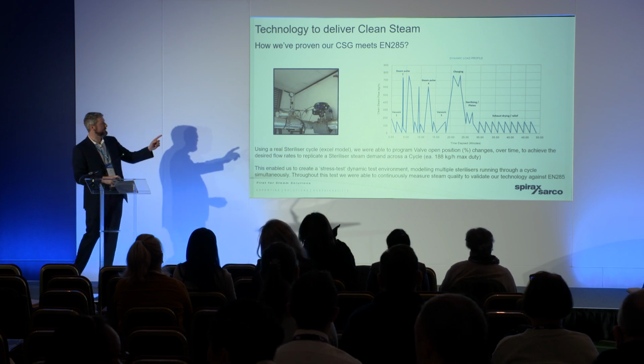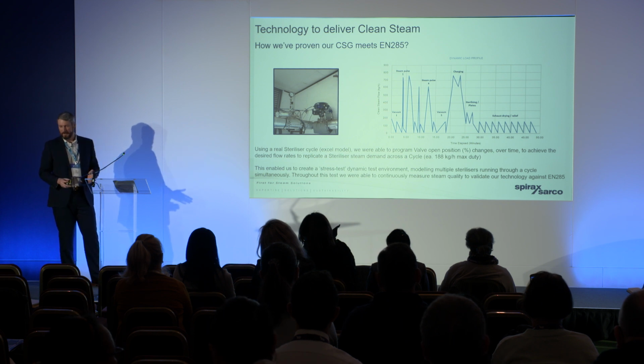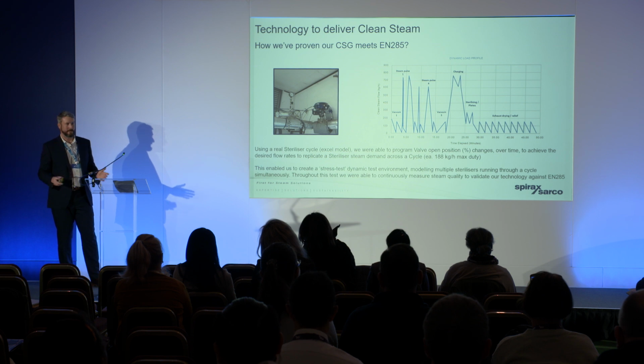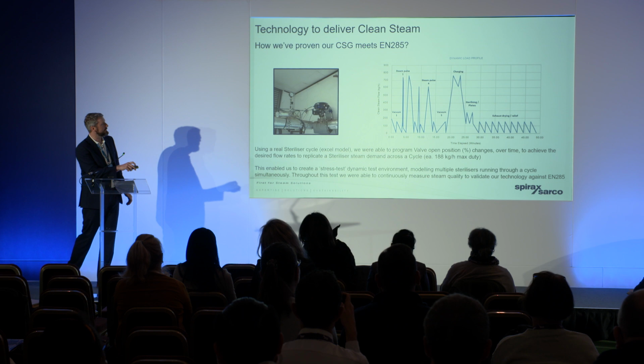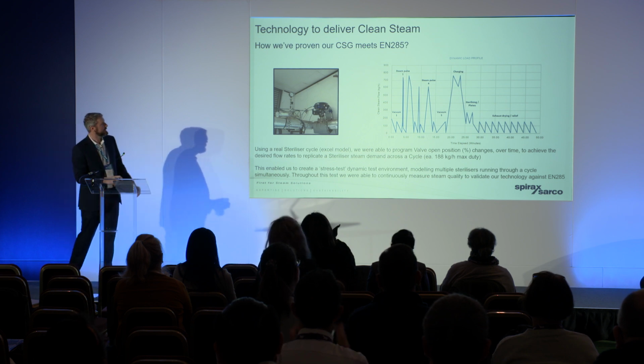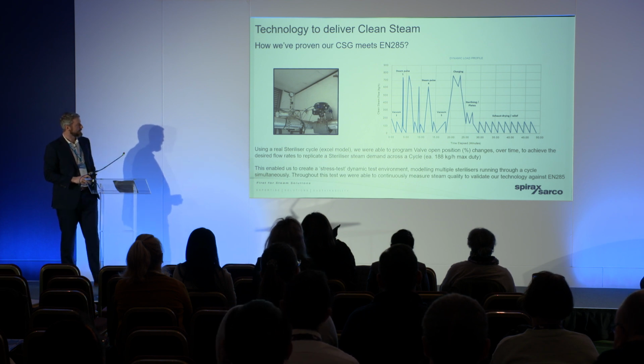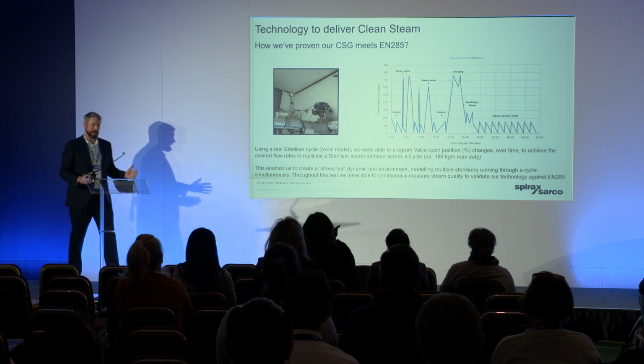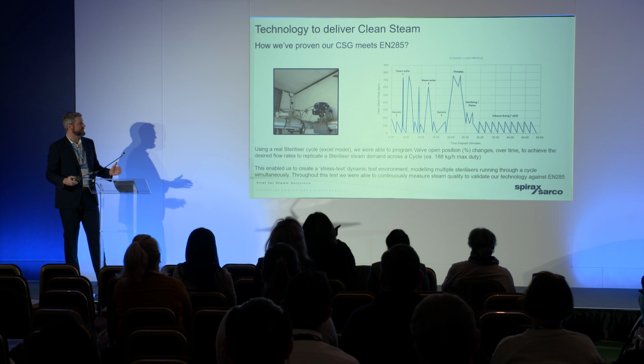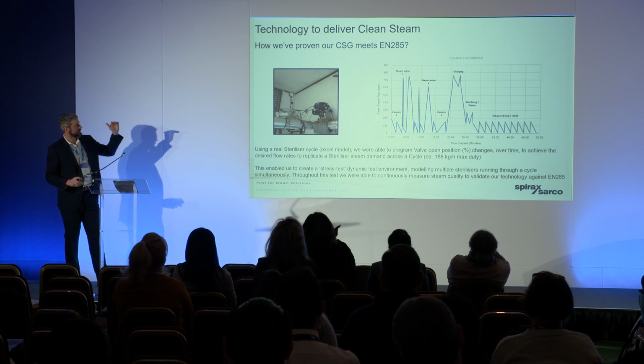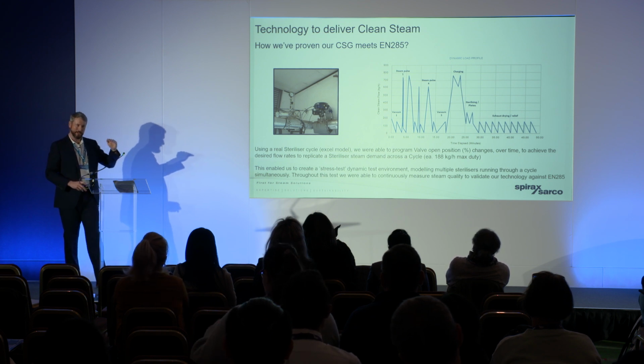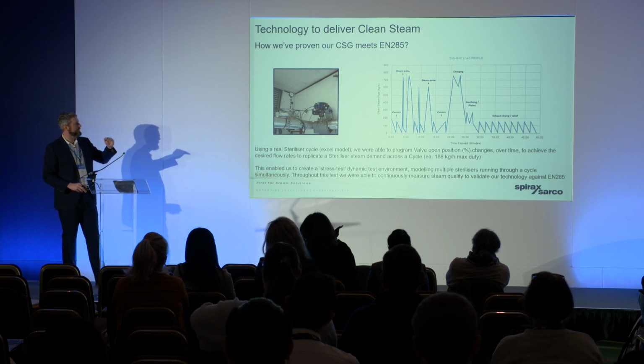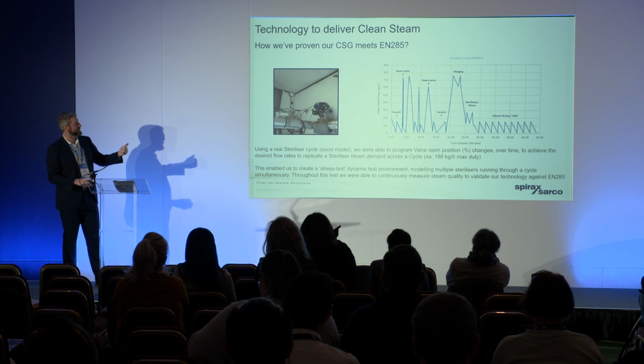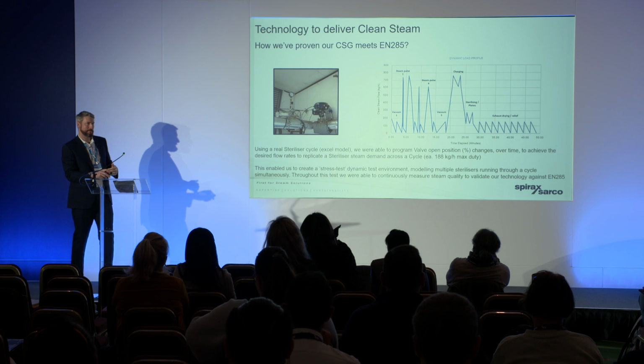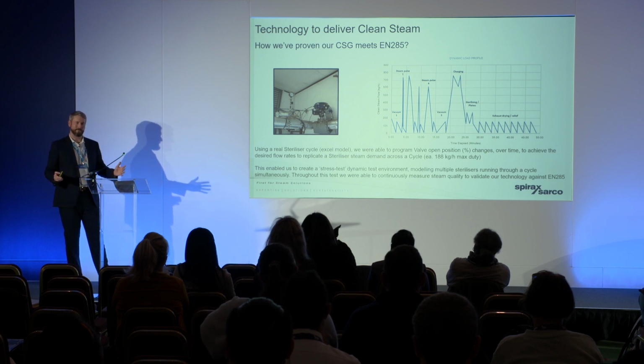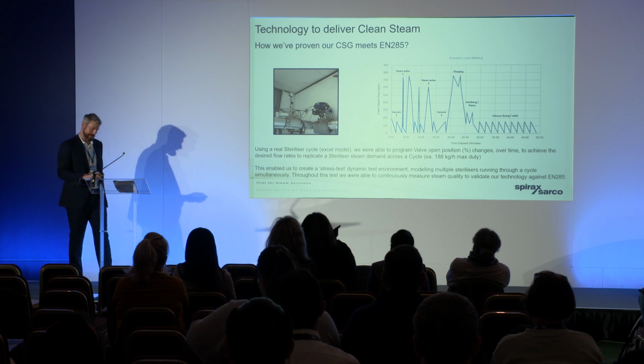We also had an Excel table model showing our steam flow rates and the time period across a sterilizer cycle. It was around 50 minutes, with a vacuum phase, steam pulses, the plateau phases and charging phases. With our clean steam generator, we had a theoretical capacity of what it could generate in terms of steam volume. We were able to take that theoretical capacity and prove that we could always achieve EN285 dryness, non-condensable gases, and superheat. Then, taking our maximum load, we were able to simulate multiple sterilizers all running at the same time, all pressing go at the same time, to create the worst case dynamic conditions.